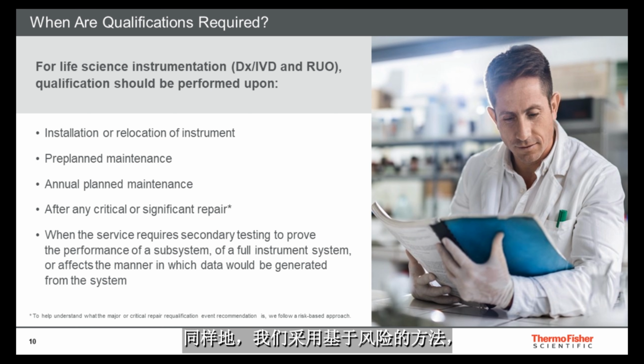Similarly, we use a risk-based approach in alignment with FDA philosophy to make a recommendation to customers about requalification after each and every service event. The determination is based on the guidance language significant to the performance of the system. Let me provide the audience with an example of how this risk-based recommendation is applied. If a field service engineer replaces a door hinge assembly, that has nothing to do with how the instrument operates or generates data, it would not be triggering a requalification. However, if the field service engineer replaces a halogen lamp, which would be changing the fluorescent intensity as well as the filter and dye calibration on the instrument, this would have an impact on the data, thus would generate a requalification. Dean, are there any equipment qualification variations from my instrument-based example?